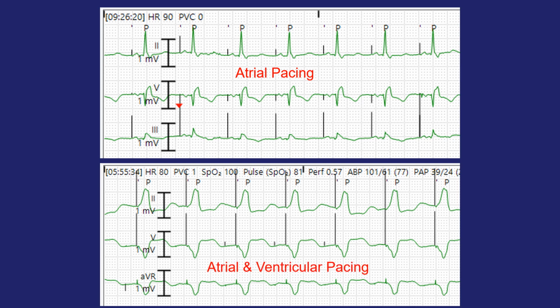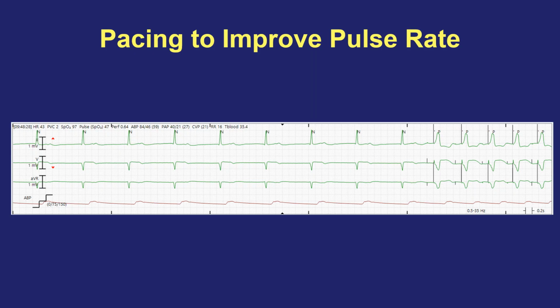Here in this bottom image, there's both atrial and ventricular pacing. You can see two black spikes drawn in by telemetry. Here in this bottom tracing, it's not picking it up, so there's a little tiny atrial pacing spike and a ventricular pacing spike. And you might see those, but again, telemetry is usually activated for pacing mode so that the augmentation, the drawings, are very prominent and there's no question when pacing is occurring.